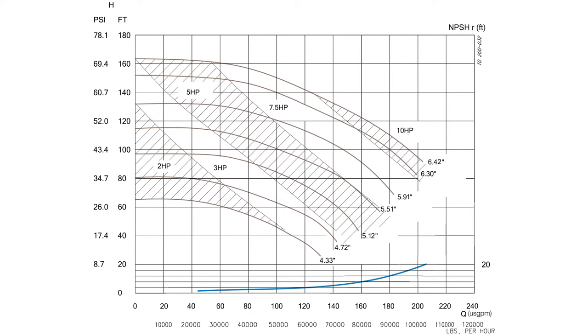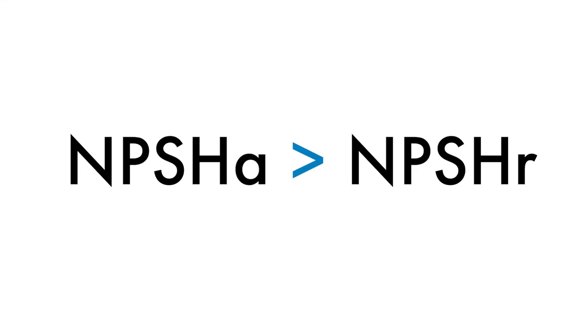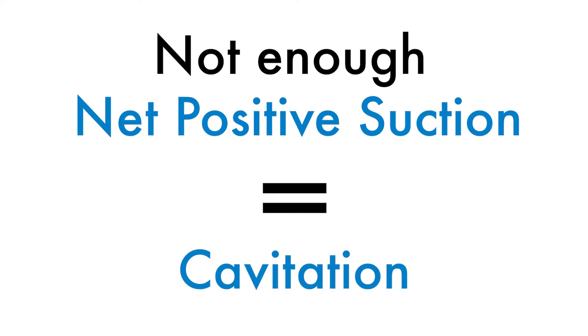The other side of the equation is NPSHA, with A standing for Available. NPSHA is determined by the process piping. You always want NPSHA to be greater than NPSHR. Without enough net positive suction, the pump will cavitate, which affects performance and pump life.